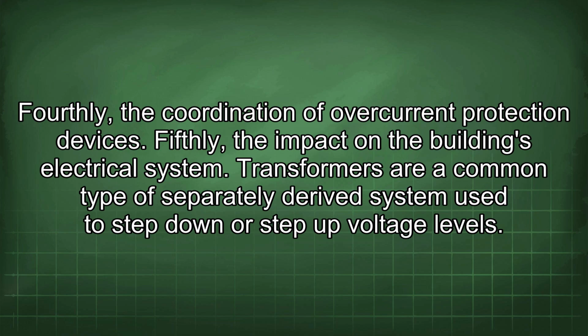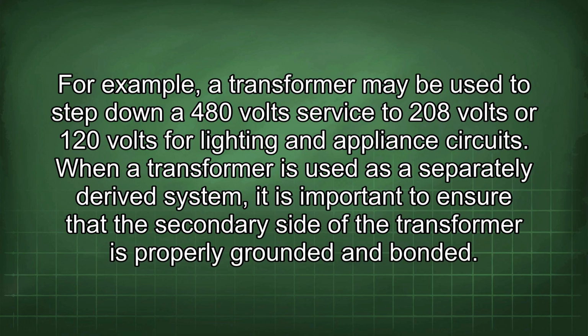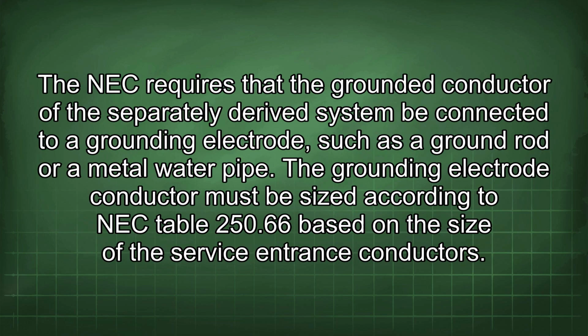Transformers are a common type of separately derived system used to step down or step up voltage levels. For example, a transformer may be used to step down a 480 volt service to 208 volts or 120 volts for lighting and appliance circuits. When a transformer is used as a separately derived system, it is important to ensure that the secondary side of the transformer is properly grounded and bonded. The NEC requires that the grounded conductor of the separately derived system be connected to a grounding electrode, such as a ground rod or a metal water pipe.